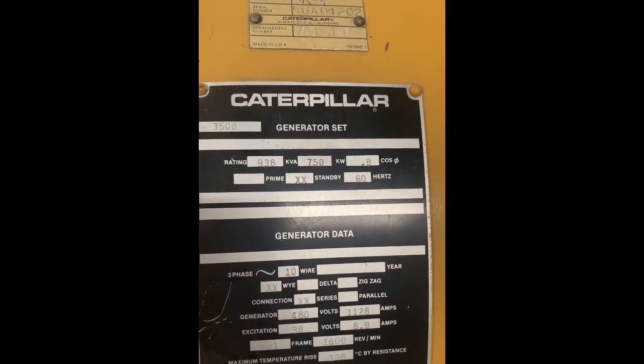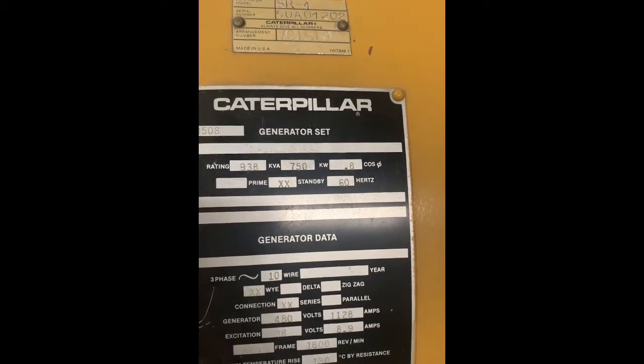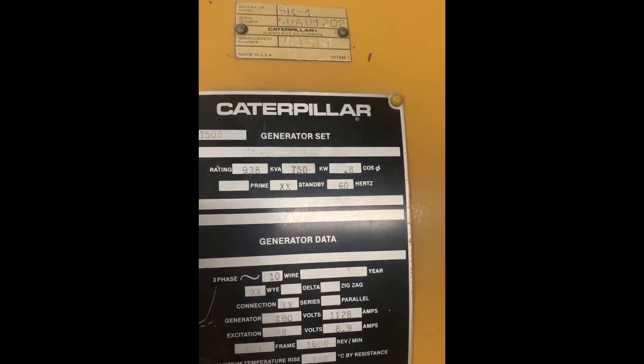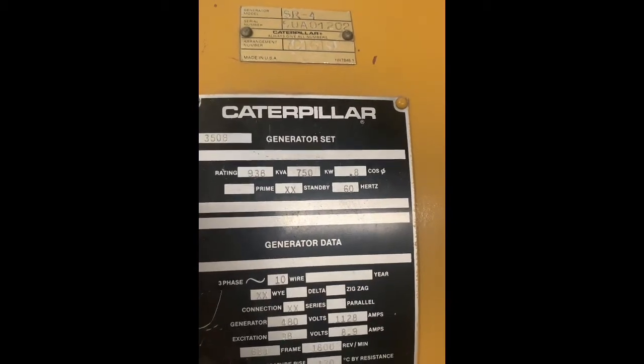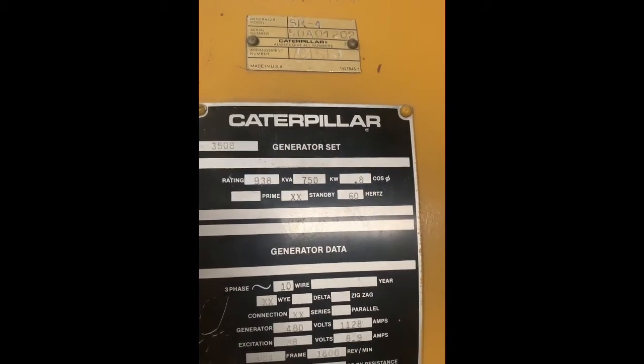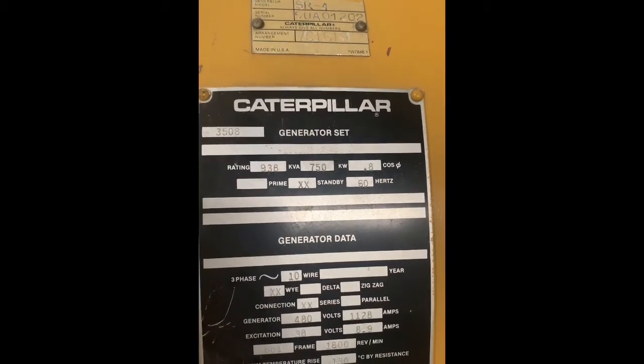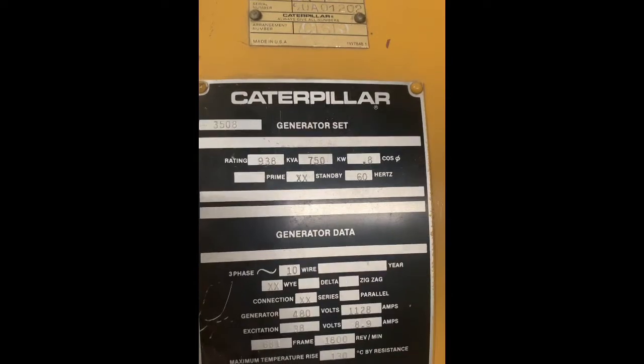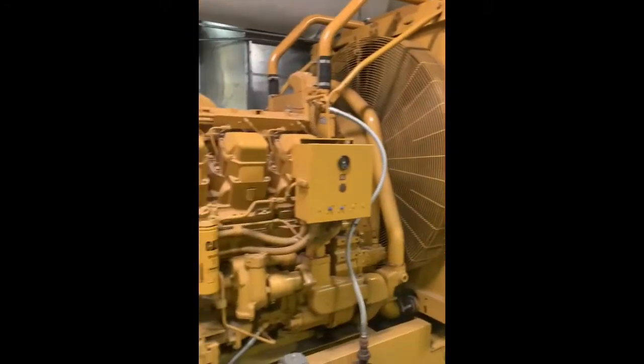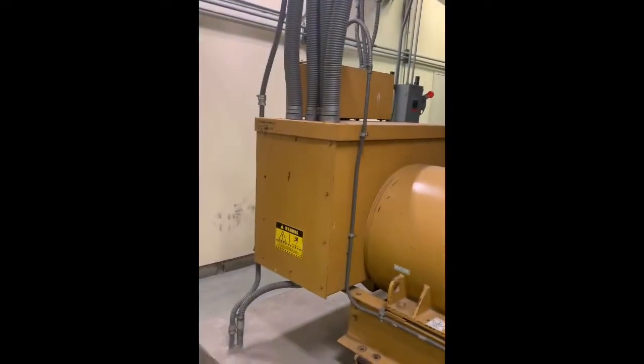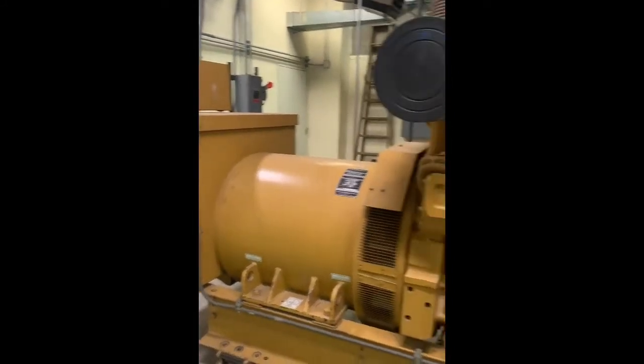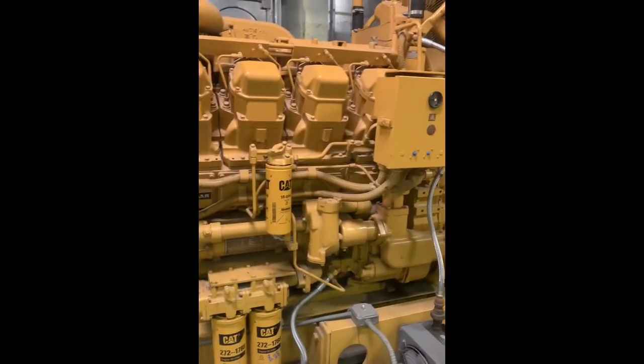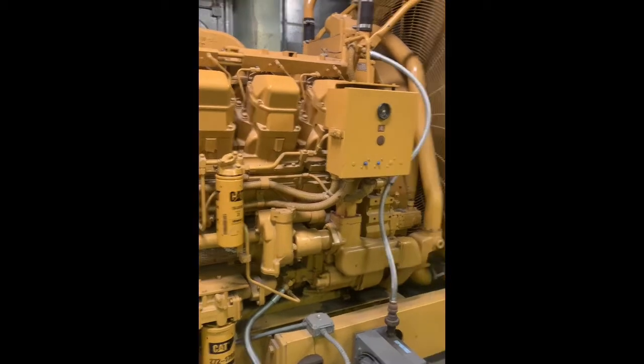So if you look, it'll tell you 938 kVA, but only 750 kilowatts. If we do that math, 938 times 0.8, it's going to give you 750. Okay, so this is a 750 kilowatt generator, which is fairly decent, but relatively tame. I worked at a data center prior to coming here, and we had 6 2,000 kilowatt generators wired in parallel.